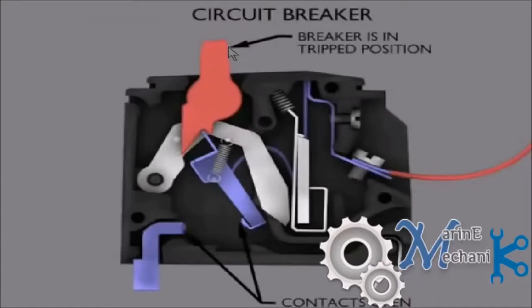After it's tripping, it's in a center position. On is towards this, off is this, and when it's in center position, it's in a trip position. You've got to reset it, and resetting depends upon the time the bimetallic strip takes to come to normal position. It has to bend back. When the current flows through it, the bimetallic strip gets heated up. When the supply is interrupted, the bimetallic strip cools down and comes back to its original position, allowing you to put off the breaker and reset it. Let's see now what happens.